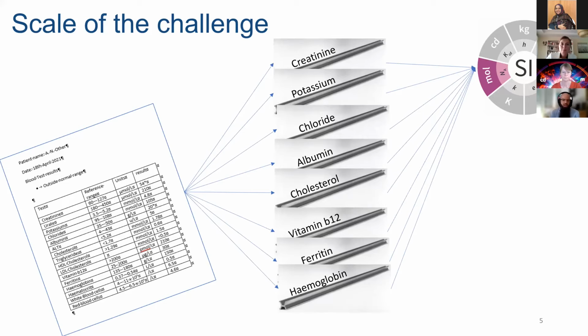And it is the case that often in chemical measurements, overcoming interferences from the background matrix provides the greater challenge in routine testing than sourcing a purified primary calibrator. And to circumvent this, in clinical testing methods, calibrators used are often present in the same matrix as the samples. They are then matrix matched.